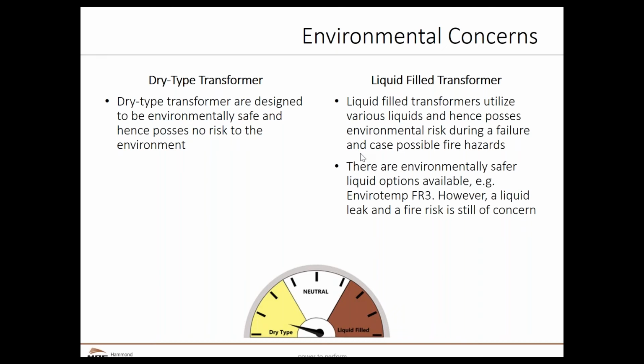Those still provide some environmental risk, environmental assessments, insurance. Depending upon the size of the transformer and how much liquid is in there, even outdoors we may have to provide some type of basin to catch the liquid should it leak out. If the liquid leaks out, even if it's somewhat benign, let's say an ester oil that might be a peanut-based or some other type of vegetable-based oil, even in those cases, environmental reports would still have to be filed. Some containment would have to be done if it spills on the ground. So there are environmental concerns with liquid filled transformers that simply don't exist with dry type transformers.